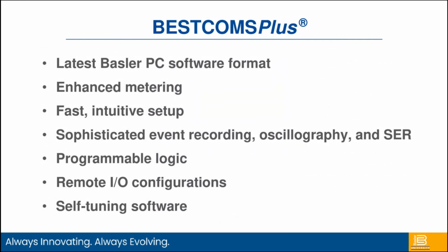Basler utilizes BESTCOMS Plus software for all of our digital products, all of our new digital products anyway. So the advantage there is if you're familiar with it from a protective relay function or a genset controller function or voltage regulator functions, if you see any of the other devices, you're already familiar with our BESTCOMS software. So it gives us a full metering. It's intuitive setup, especially once you're familiar with it. And again, we can do the event recording, oscillography, sequence of events. It has the fully programmable logic. It can allow for remote I/O configurations if they're available for that particular product, and again, our auto tuning.